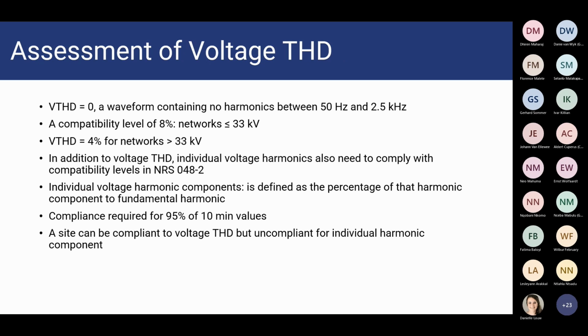Cool, thanks, Randolph. So if you have an example or case where your voltage THD is 0, that in concept means that the waveform doesn't contain any harmonics up to 2.5 kilohertz. Now, practically, you will never see that, but that is the ideal case. But it doesn't mean there aren't harmonics above 2.5 kilohertz. So just take note of that.